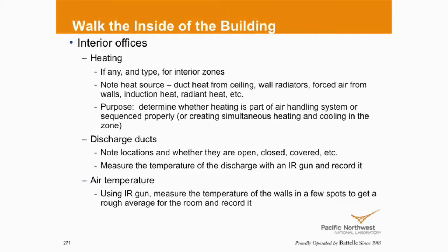Discharge ducts. Do we see that someone's taken cardboard? Are they adjusted right? In the small building retuning, we talk about looking for signs of dust on the ceiling. What's that indicate? Do we have filtration issues? If we get up above the ceiling, do we find ductwork that's come loose? We typically, at this level of training, don't emphasize that.